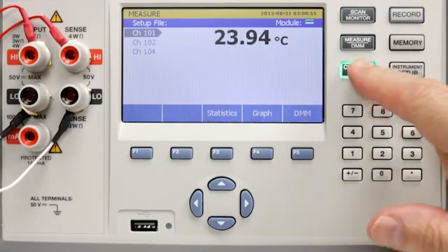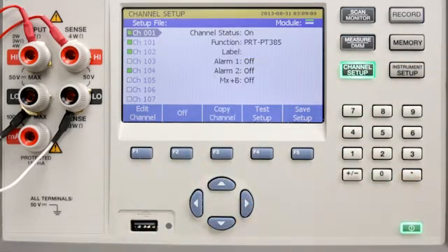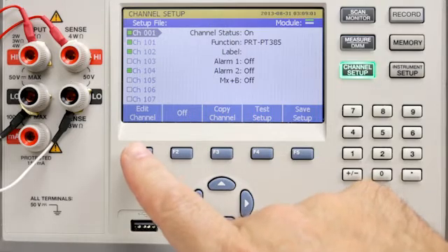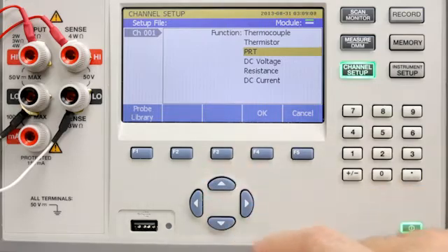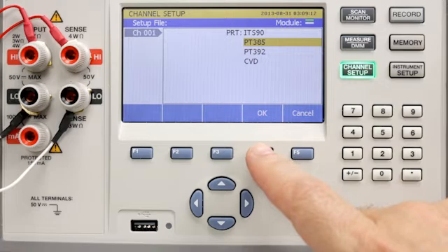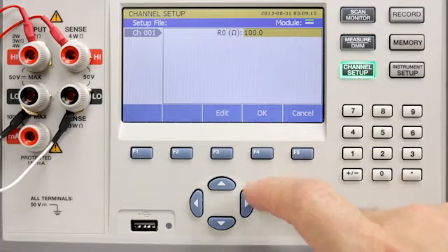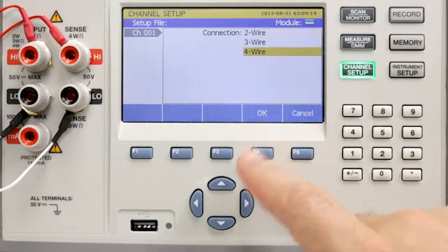Press channel setup. Set channel 1 to on. Select edit channel. Set function to PRT. We'll choose PRT PT385, set the resistance value to 100 ohms and choose 4-wire PRT.